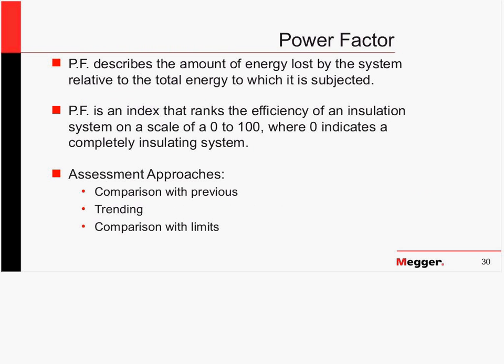Power factor is simply describing how much energy gets lost by the system when we apply some total amount of energy to it. So how much of the energy we apply gets lost when we energize the system. It's an index. It ranks the insulation system on a scale of 0 to 100, where 0 would indicate a completely insulating system, and it's reported in percent because usually the number is very small. So we multiply by 100 to deal in percent, so that is a more tangible measurement or index.